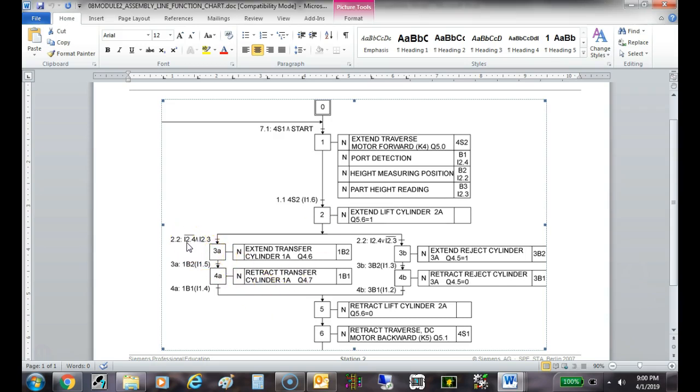If input 2.4, I wish instead of putting the actual input, they should have put the actual sensor number over here. You see what I'm talking about? So instead of putting B1, they actually put input 2.4. So this says input 2.4 is not true, so it didn't get a reflected light back, right? Understand?